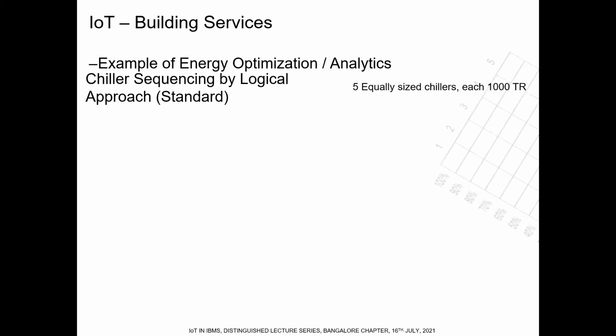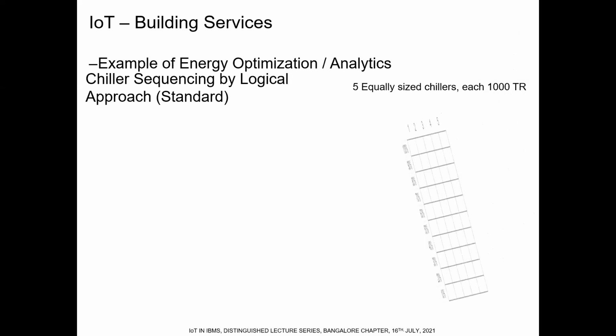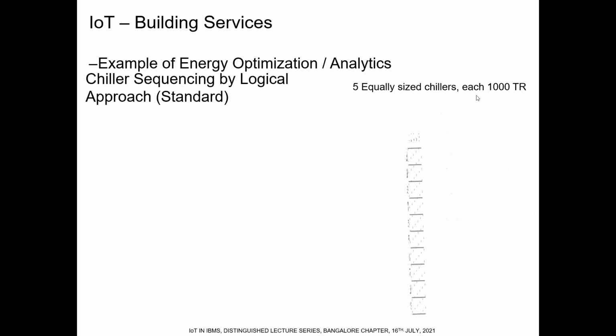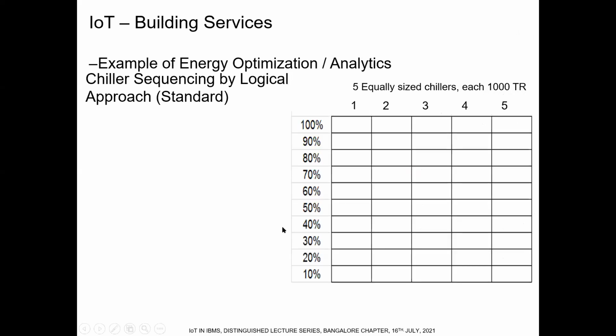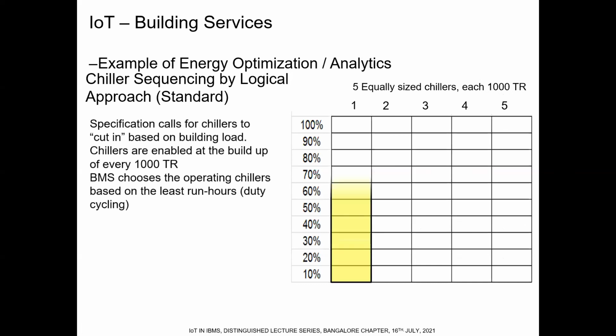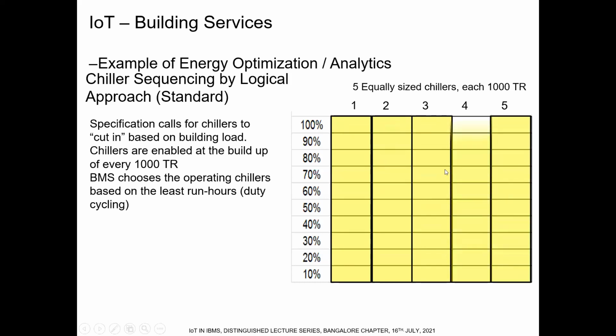The first step is the common automation process in the BMS field. Let us say in this building, there are 5 equally sized chillers with 1,000-ton capacity each. That means the building has an installed capacity of 5,000 tons. That is how it turned out. The sequencing is done based on the increase in load. You can see the first chiller started, then 3 started, then 2 started, 5 started, and 4 started.